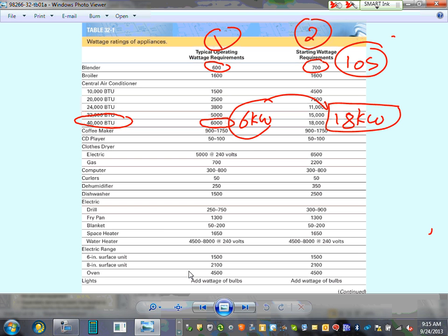So you can reduce the size of your generator by starting the equipment gradually, in steps. Start this load first, wait a couple of seconds, five. We're not waiting like an hour. You're talking about 10 seconds max. Ten seconds is typically what it takes any load to start up and be running. Then flip the second switch, then the third switch. By doing it this way, especially if it's machines, you reduce the size of your generators.